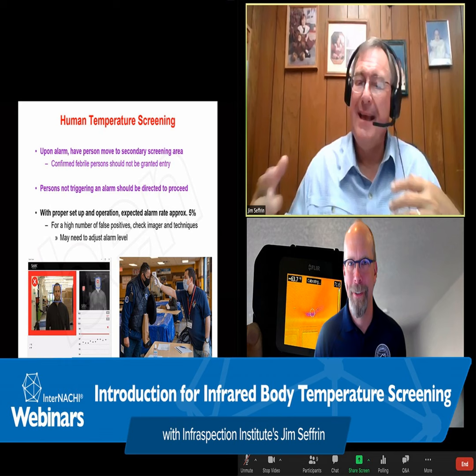When it comes to selecting a thermal imager, the United States Food and Drug Administration has strict requirements for medical equipment. Prior to the 2019 pandemic, sorry, we're calling it 2019 because it started in 2019, but it's the one we're currently engaged in. So prior to the current pandemic, imagers were required to have a 510K clearance. I had mentioned this before. This was intended to ensure that the device was suitable for its intended use. In order to obtain a 510K clearance, the manufacturer had to comply with rules for the marketing of the device in the future, as well as making sure that it was suitable for its intended use at the outset. For those of you that own FLIR systems, thermal imaging systems, you may find, if you check with FLIR, that the instrument you currently have may likely have a 510K clearance already. So prior to purchasing a system, ascertain if the imager has a 510K clearance.